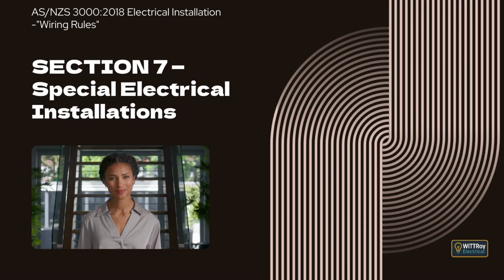Clause 7.2.4.4 Identification. This clause explains that all switches operating in the supply circuit to safety services must be clearly identified so it is obvious which safety service they control. It explains that main switches for safety services must be identified as a main switch, must clearly indicate the safety service equipment they control using uppercase lettering, must be marked with the words "in the event of fire do not switch off" in uppercase, and must also be identified by contrasting color or another suitable method so they can be quickly recognized.